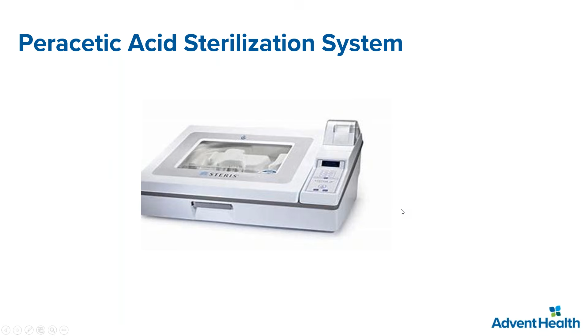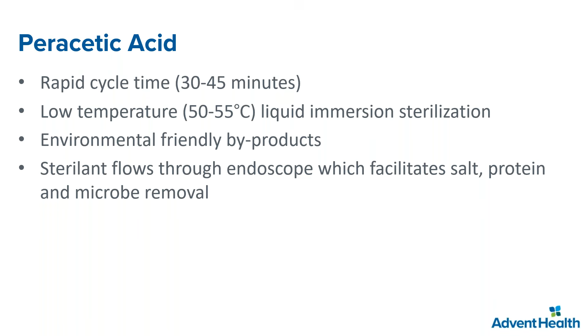The peracetic acid or the STERIS system is a very rapid cycle as well. It's low temperature. It's a liquid immersion sterilization. It's environmentally friendly, and also the sterilant flows through the endoscope, which facilitates salt, protein and microbe removal. However, one of the disadvantages is that it is a point of use item: whatever you remove from that system needs to be used immediately. You cannot save that. And it's also used for immersible instruments only.